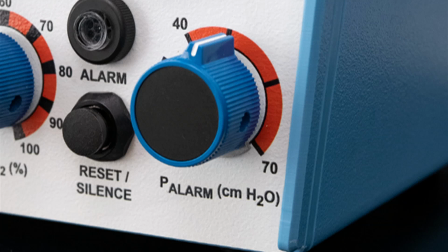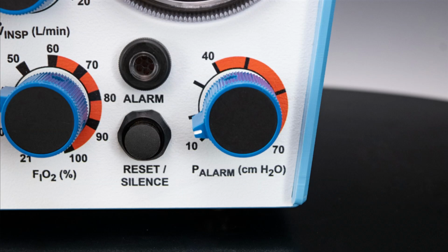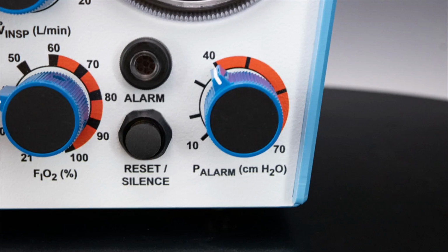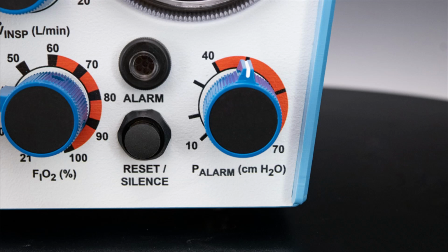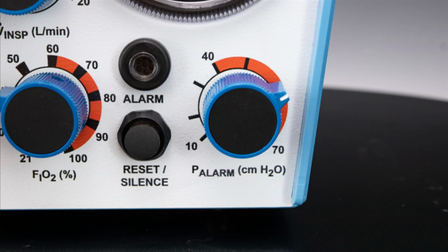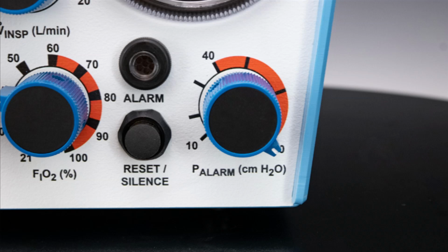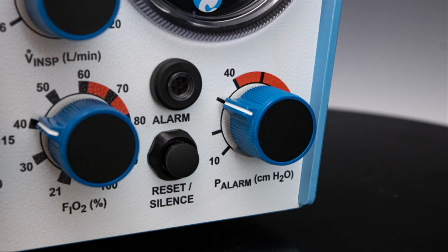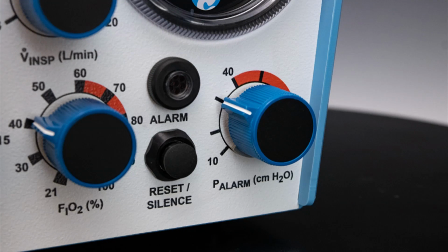High patient pressure alarm. In the lower right corner of the front panel is the P alarm, or high patient pressure alarm. During mechanical ventilation, the high pressure alarm will provide an audible and visual alarm when pressure reaches the control set level from 10 to 70 centimeters of water. The control is set independently of the peak pressure control.